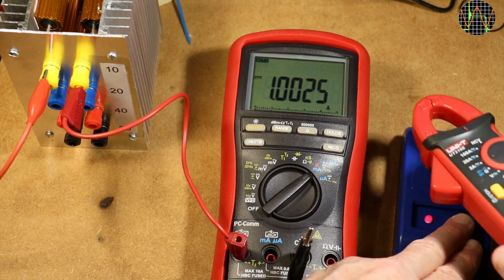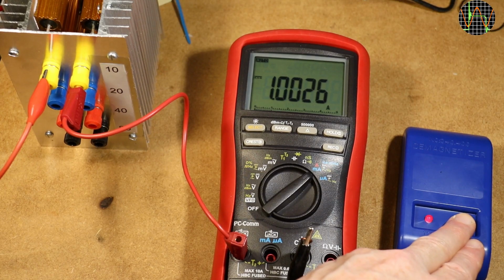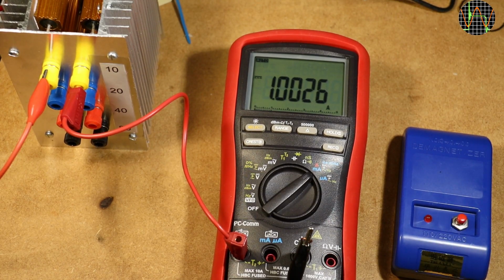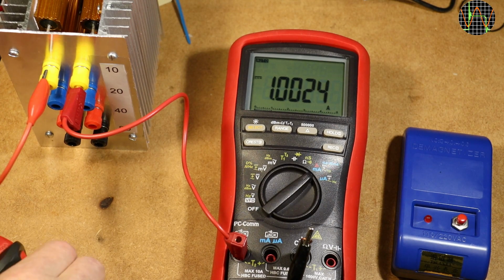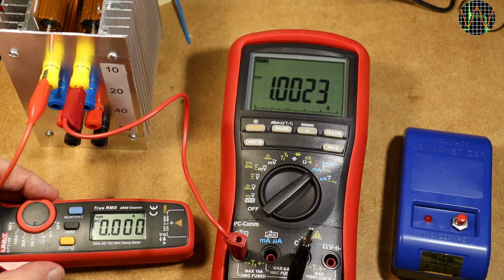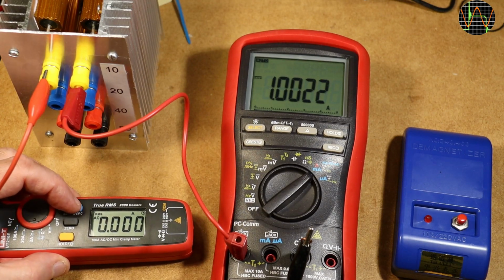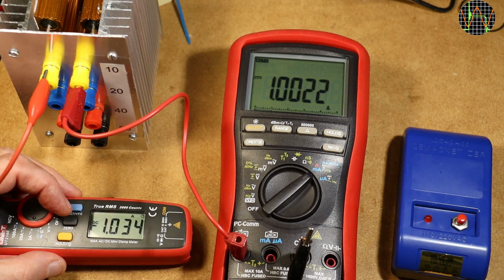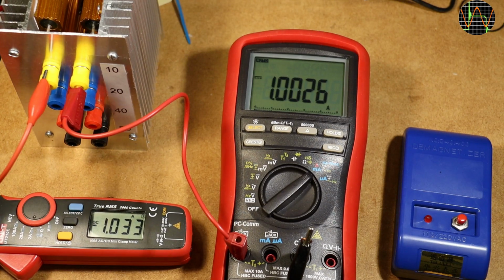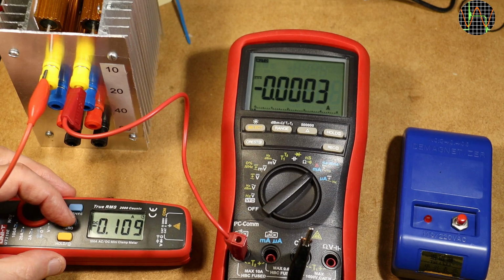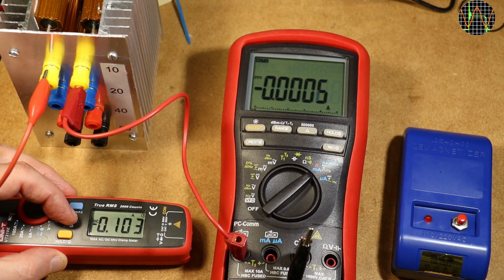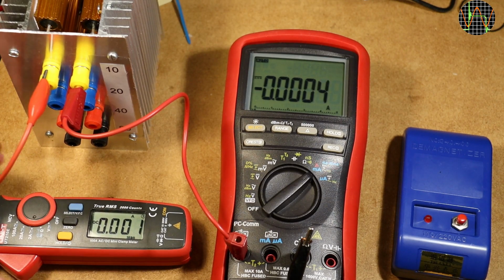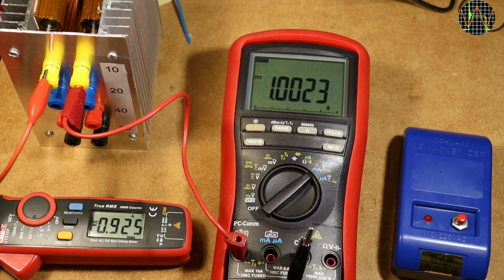I use this blue demagnetizer from China, which produces a very strong magnetic field changing direction at mains frequency, and by moving the meter away from it, the magnetism induced by this constant pole-changing magnetic field gradually diminishes in strength, leaving the meter demagnetized. Once demagnetized, the clamp meter needs to be zeroed again to compensate for the Earth's magnetic field. The reading is slightly higher than before, but still way too low. So residual magnetism is not the problem.